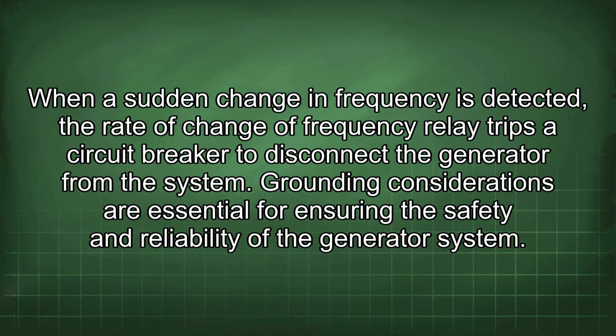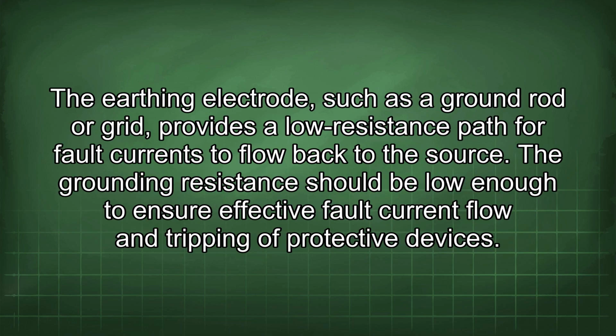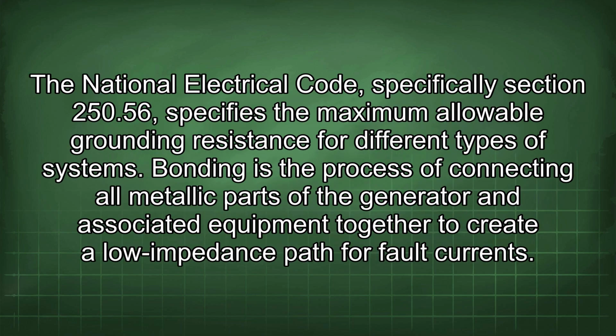Grounding considerations are essential for ensuring the safety and reliability of the generator system. The earthing electrode, such as a ground rod or grid, provides a low resistance path for fault currents to flow back to the source. The grounding resistance should be low enough to ensure effective fault current flow and tripping of protective devices. The National Electrical Code, specifically Section 250.56, specifies the maximum allowable grounding resistance for different types of systems.